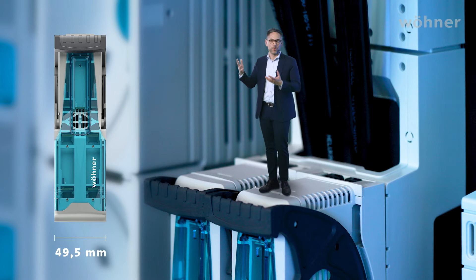With our slim NH000 fuse switch disconnector, we've taken miniaturization to its absolute limits. We've got it down to 49.5 millimeters. You can't get slimmer than that. Fully functional, safe to operate and compliant with all clearance and creepage distances. Any slimmer and the outside would need to be smaller than the inside.